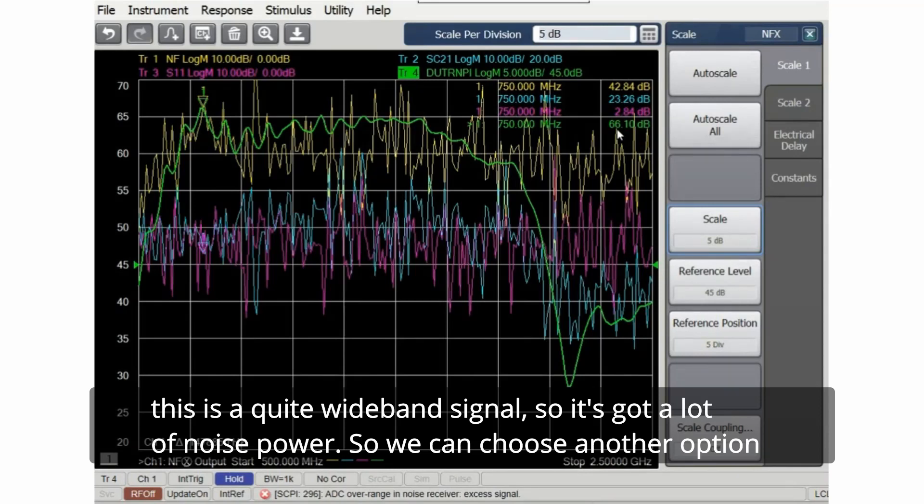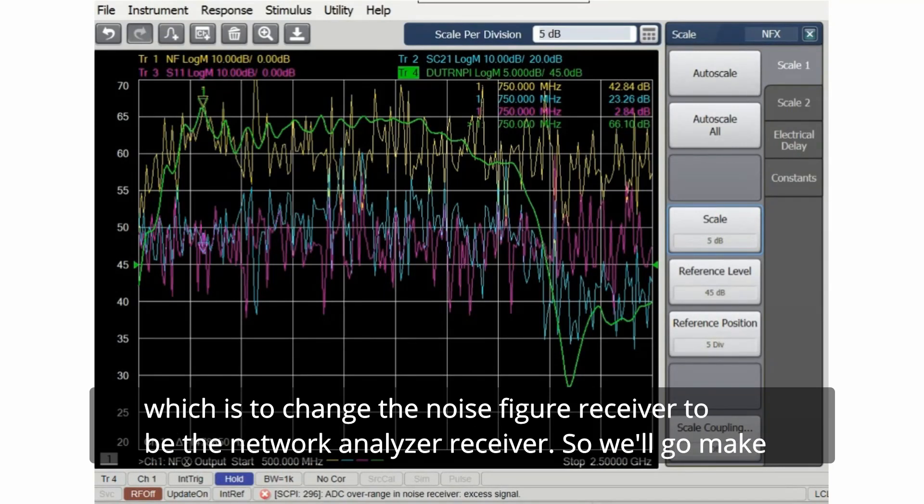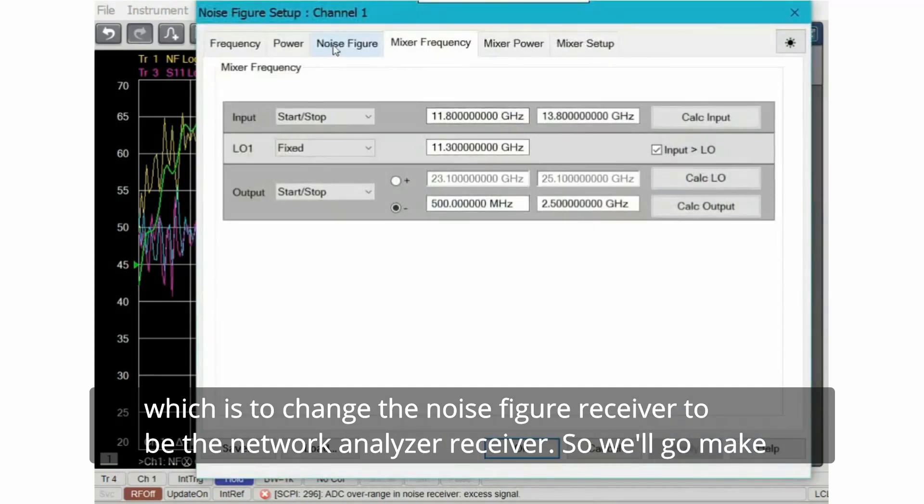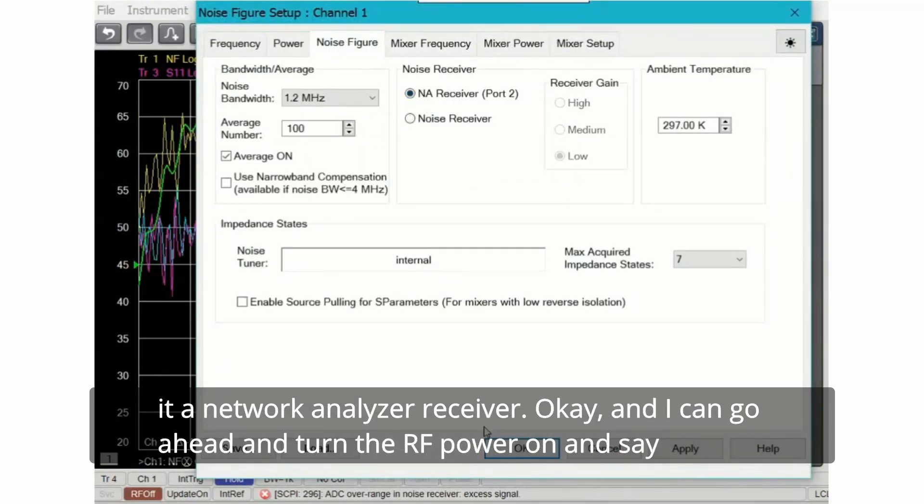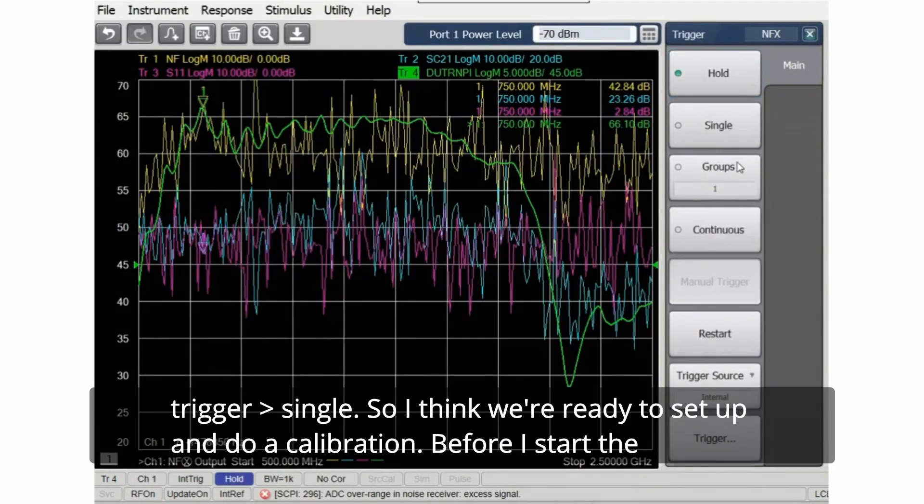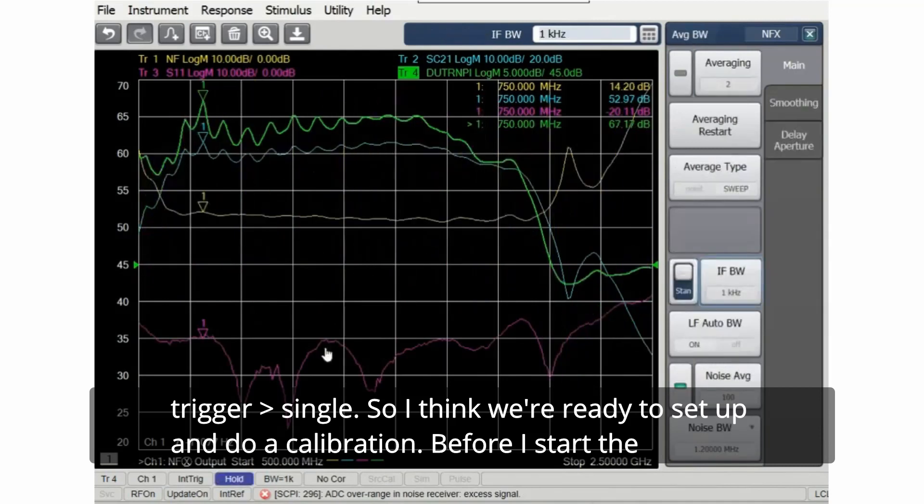So we can choose another option which is to change the noise figure receiver to be the network analyzer receiver. So we'll go make it a network analyzer receiver. And I can go ahead and turn the RF power on and say trigger single, so I think we're ready to set up and do a calibration.